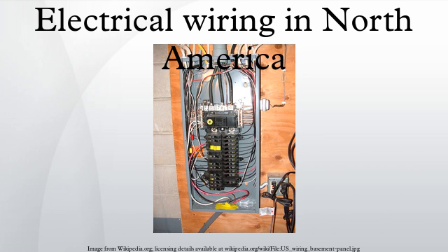Jurisdictions permit use of non-metallic sheathed cable. The NEC does not permit use of NM cable in large, fire-resistant, or high-rise structures. In Type NM cable, conductor insulation is color-coded for identification, typically one black, one white, and a bare grounding conductor.